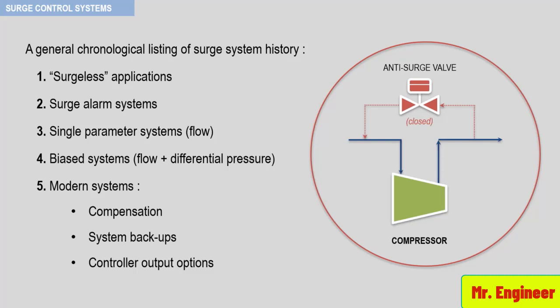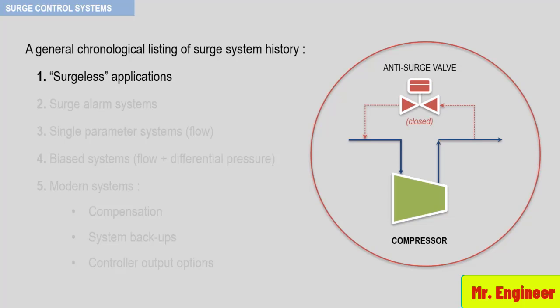Let's start with the first system. In my professional experience, many so-called surgeless applications have been observed. These are applications where the process designer assesses the system and concludes that there is no possibility to surge the compressor. Many times, this assessment is based on system resistance alone. The conclusion being that since there are not any variable resistance points in the process system, like valves, coolers, or reactors that can foul, then the compressor cannot surge.